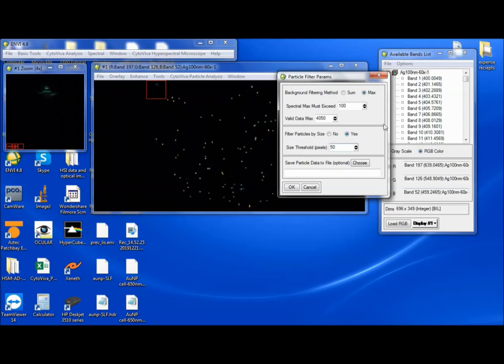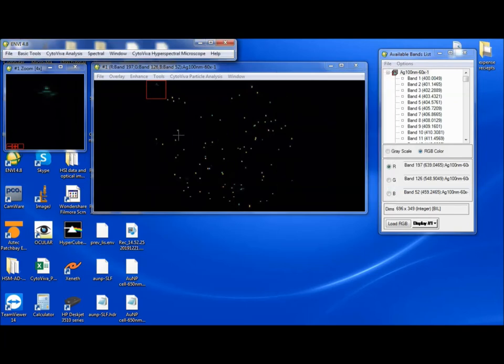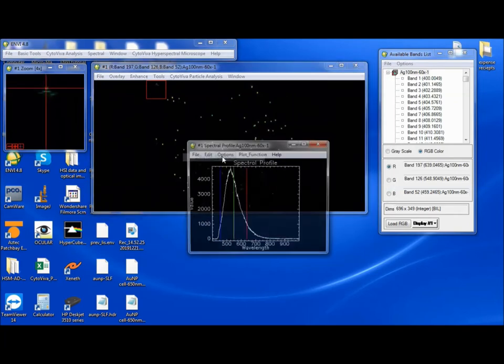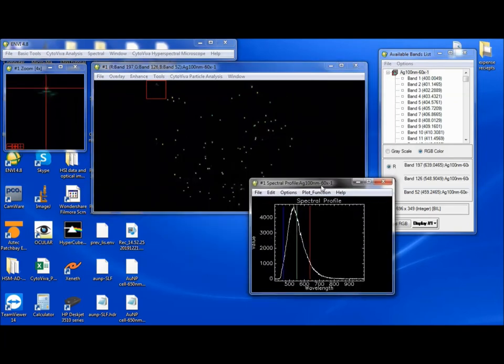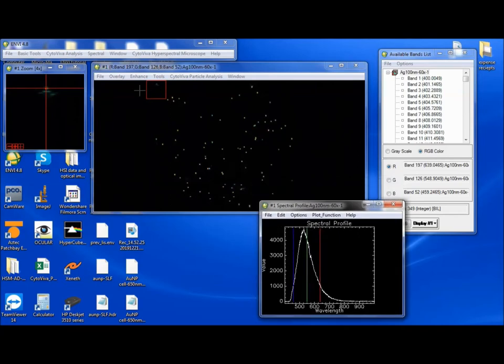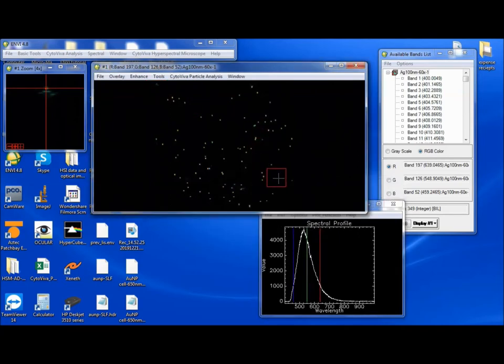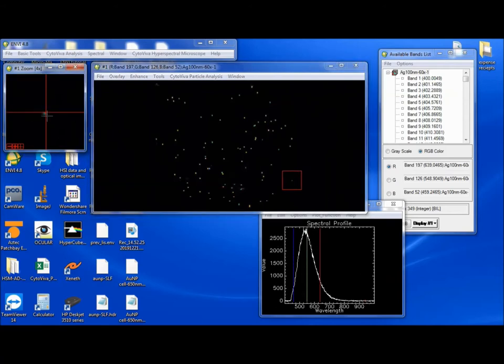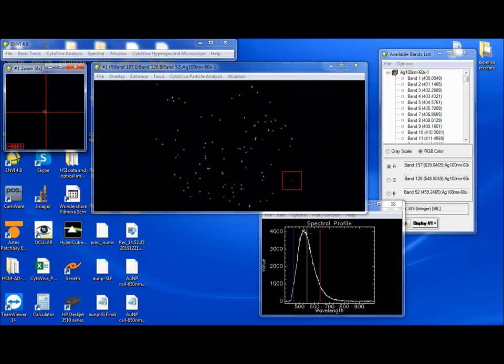So that's something that you'll have to decide and play around with. But first, let's look at this spectral max and see. So in order to access the window to pull up the live spectra, you have to close this or already have this open. So here what I'm going to do is I'm just going to go look around and there's a particle down here to the bottom right that's kind of dim. Let's see what the threshold is on this guy. So it looks like it's around 4,000.